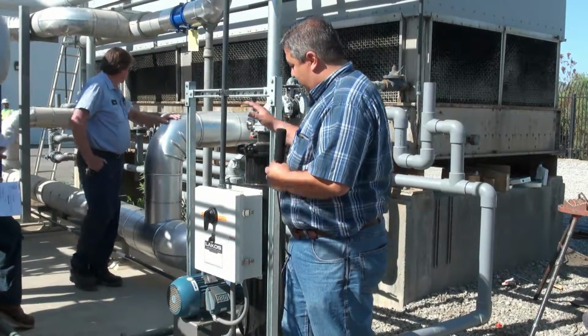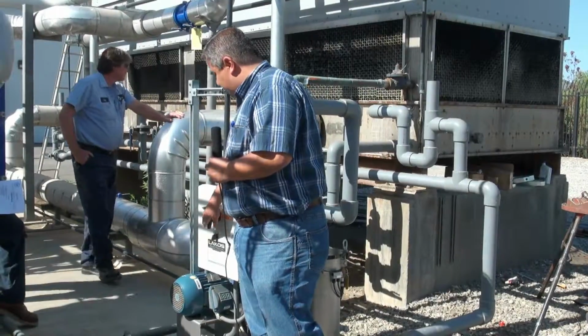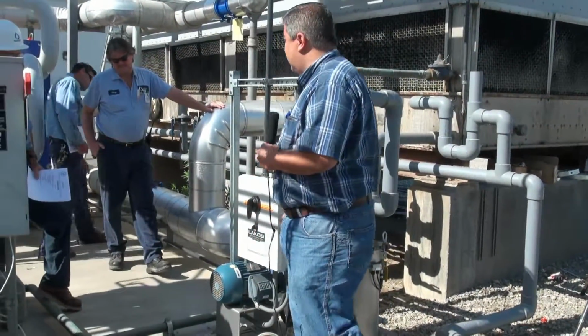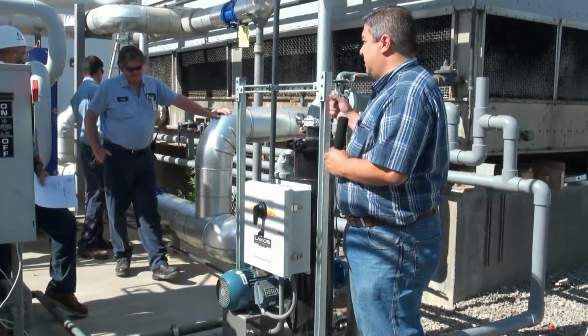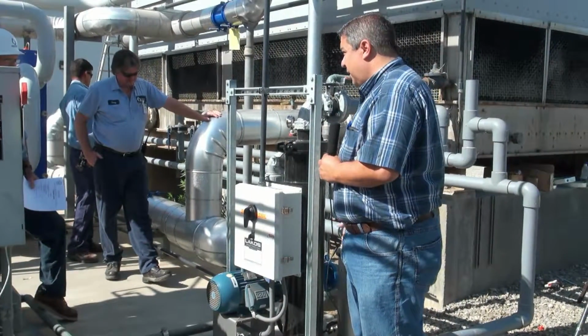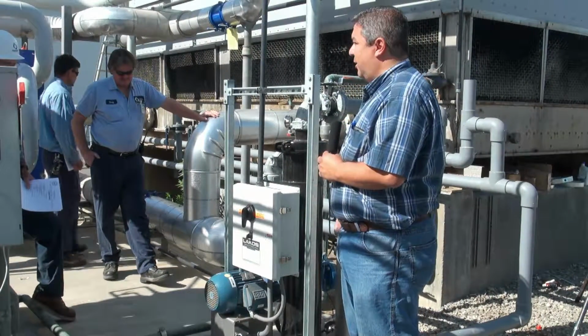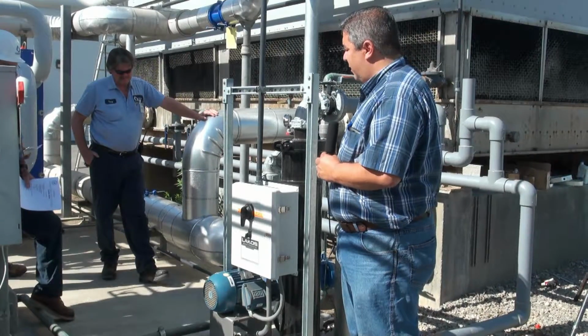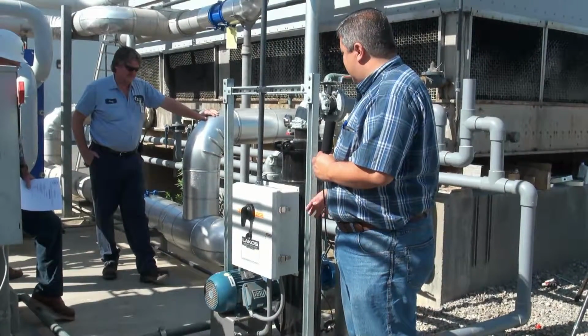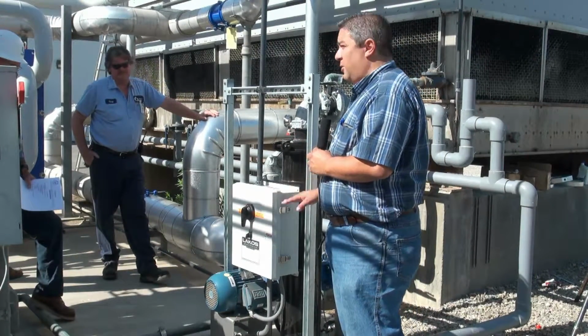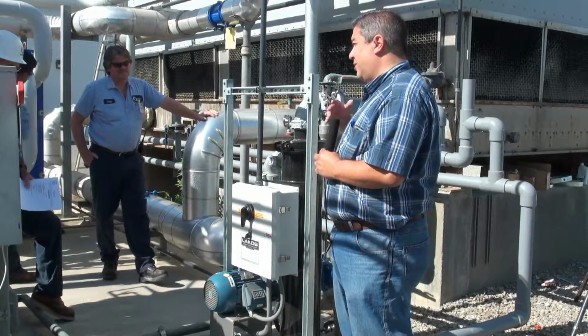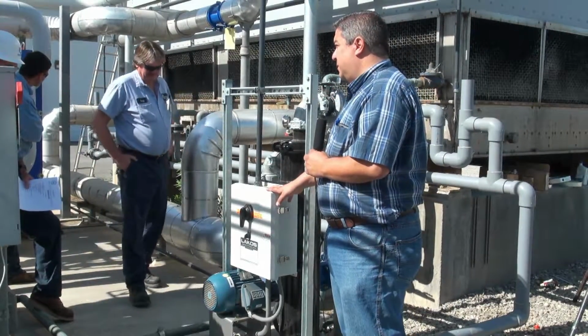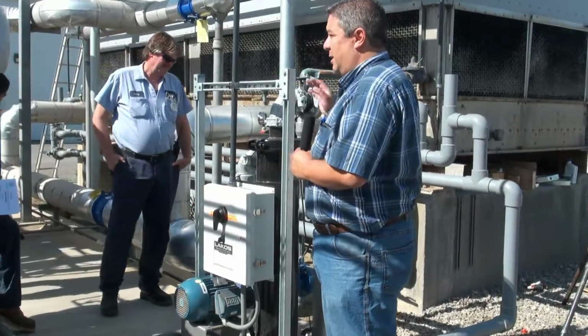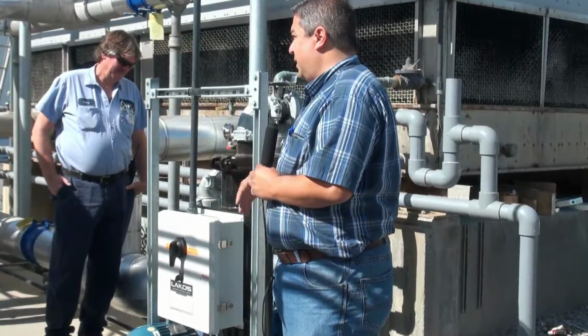It has a control panel with a disconnect switch and a hand-off-auto switch. You're not automated on this, it's fully in hand, but it can be if you'd like, that's something you guys can do later if you want. Like I said, it doesn't affect the operation of your tower at all. You can turn it on and off all you want, it's just a separate little pump system that's cleaning your system. So if the tower's running, you can leave it off or on, turn it off, whatever your case is.